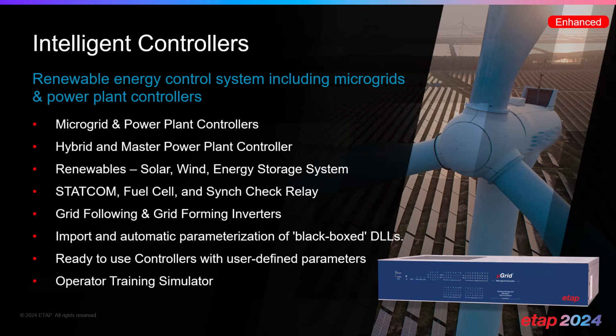The controllers are used to model microgrid and power plant controllers, but they can also be used to model hybrid or master power plant controllers, including a mix of load, renewable energy, and energy storage. They can also model STATCOMs, fuel cells, sync check relays, and grid following or grid forming inverters. You can also import and perform automatic parameterization of black boxed controllers provided by vendors with proprietary logic, and use these controllers for operator training simulators.